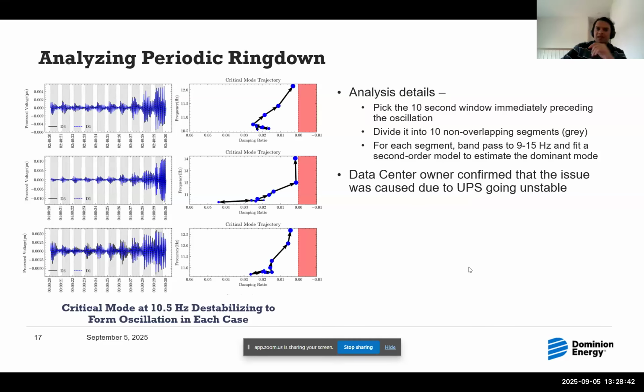So what we did is pick up the periods leading to an oscillation in all 10 events. Since the excitation happens every second, like a forcing impulse every second, we took this window of data and chopped it into non-overlapping sections of less than 1 second each, to estimate the ring down mode, or the dynamics triggered each time a transient input happens.